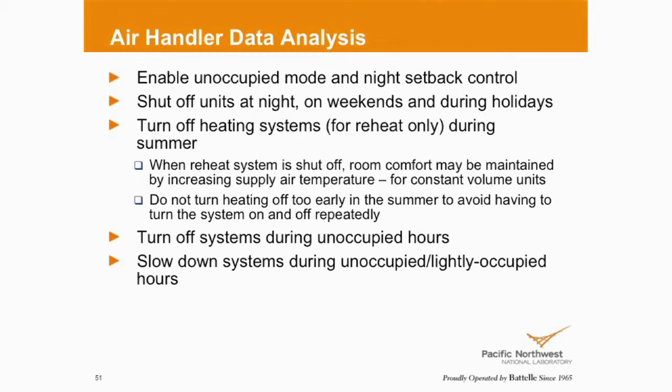So we want to enable the unoccupied mode. We want to see the fans shut off if possible. If not, we want to at least see the terminal boxes that aren't occupied shut off. Nights, weekends, holidays. Huge opportunity. It's the simplest thing to implement, and it's often not used effectively.